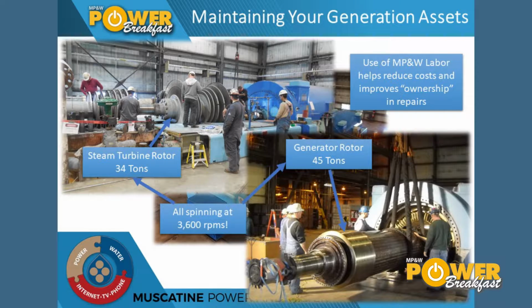Right now we found some erosion on some of these turbine blades that requires us to send this rotor off-site to a shop to be repaired. This is the first time this piece of equipment has been shipped off-site since it went into service in 1983. So if you would just collectively knock on wood, cross your fingers, say a prayer, whatever you choose, to hope for a nice safe delivery to Dallas and then back after the repairs are completed.